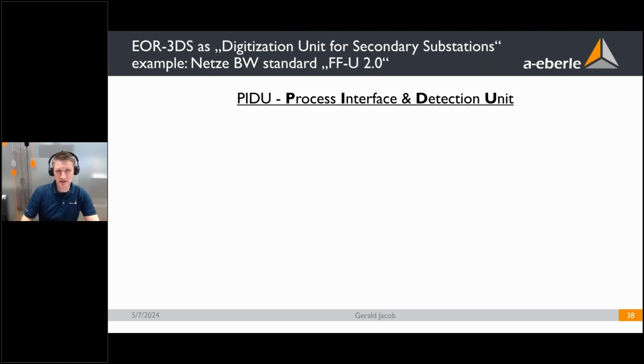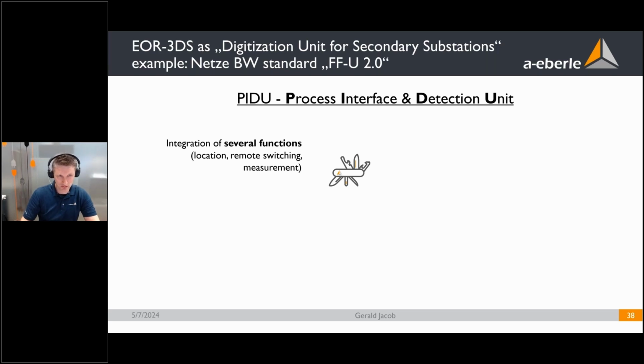What does it mean to have not only a detection unit but also a process interface? On the one hand, of course, this is our main topic, integration of several functions. So location means earth fault location, remote switching with the relays and the binary inputs, and measurement. Our device can measure with an accuracy of more than 99.5%.